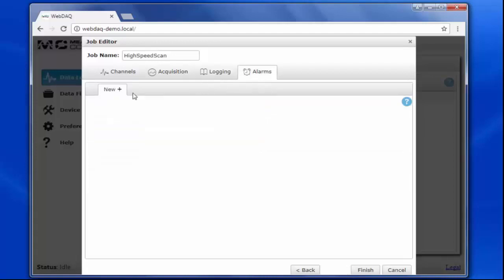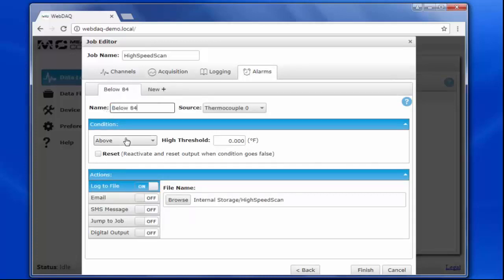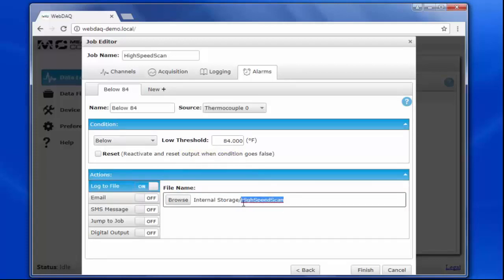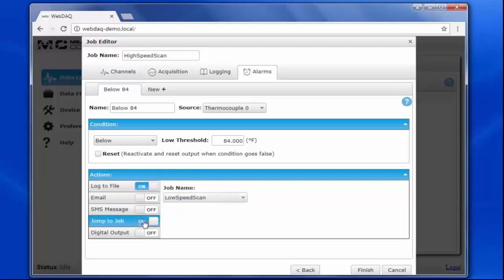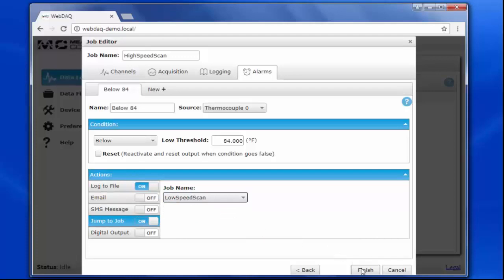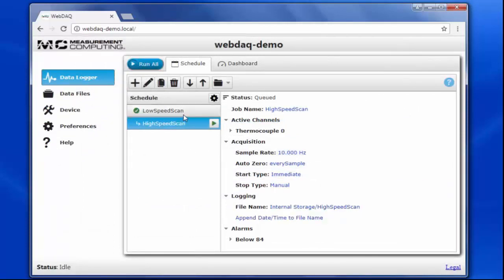Now let's look at the alarm conditions. To make sure I switch back to the slow acquisition when the temperature drops back below my threshold, I'll set an alarm for below 84 degrees Fahrenheit. I still want to log the alarm to a file. Let's name it Switch Jobs on Temp Limit. This time, we're also going to add an action to jump to our low speed job. Now I have a second job that acquires data at a faster rate, then switches back to the slower rate job once the temperature drops back below our threshold.